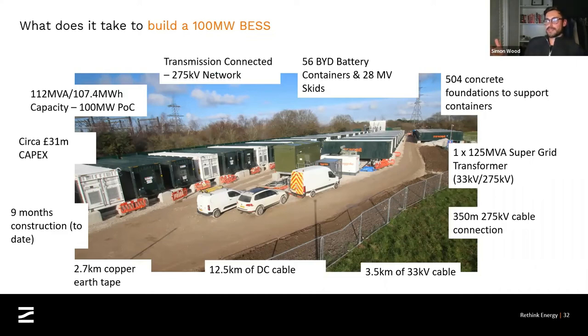So what constitutes a battery energy storage? Well, we've already mentioned the connection and the capacity, but on this site we use BYD battery containers. They're the containers in green on the screen there, and they are packed full of battery modules. A module consists of the individual cells packaged into a rectangular module, and they are then positioned in racks and arrays. They're all linked together with DC bus bars, and then controlled through a central BMS, battery management system. Each of those containers not only contains the battery cells and the modules, but it also has all the ancillary equipment: HVAC systems, fire detection systems, all of the control systems that we've mentioned. So they're a fairly self-contained unit.